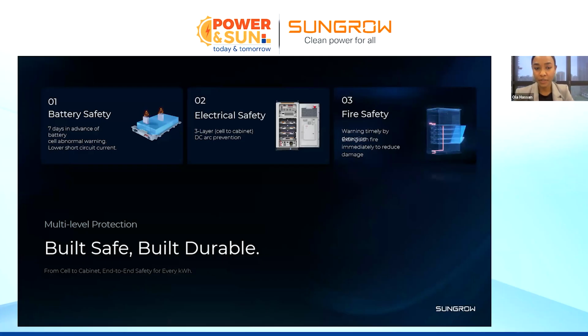And when it comes to the energy storage itself, the battery racks, we have battery cell level monitoring. So the battery cell level monitoring allows you to see if there is any fault happening on the battery side, there is a high temperature, there is some kind of arc. So there is active monitoring and active protection as well, where if there are any major alarms or hazards, the system will shut down itself and create an alarm notifying the end user or the installer about the fault and what the reason for the fault is and how to correct it. Also, there's a fire suppression system, actually a fire extinguisher, inside the cabinet itself.